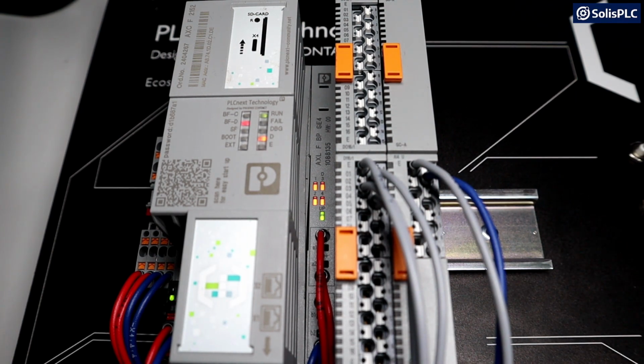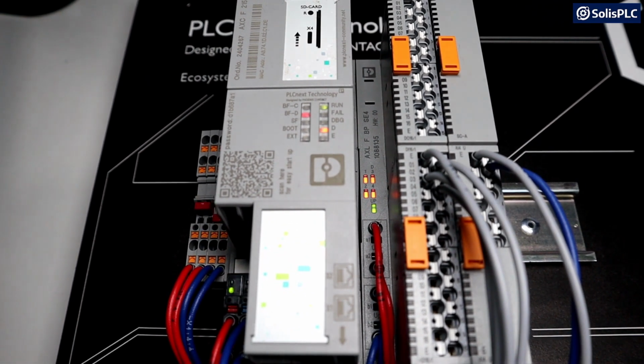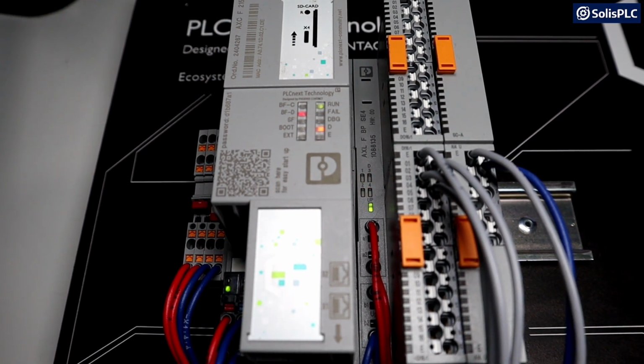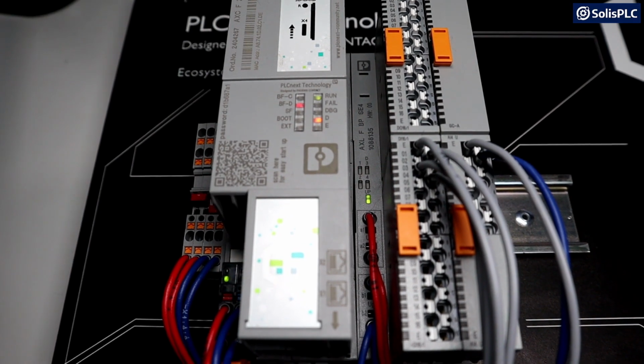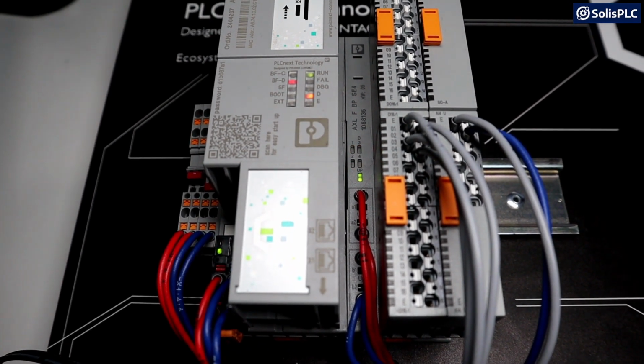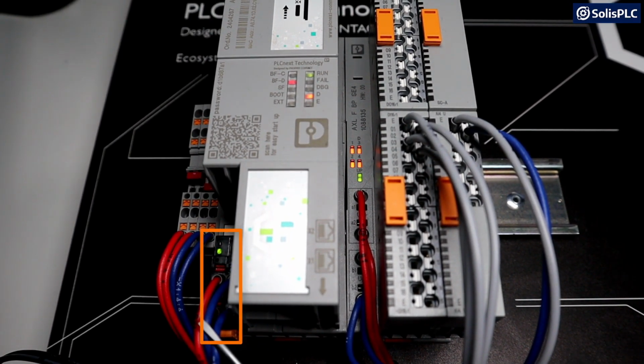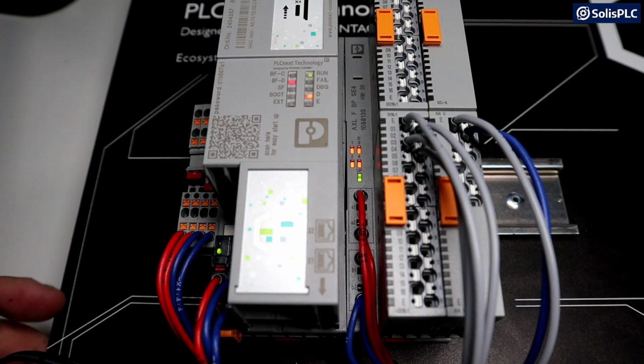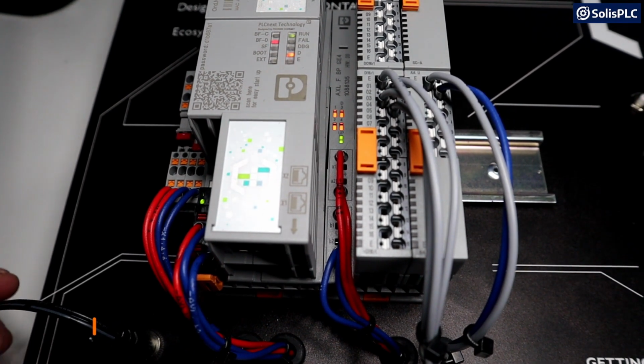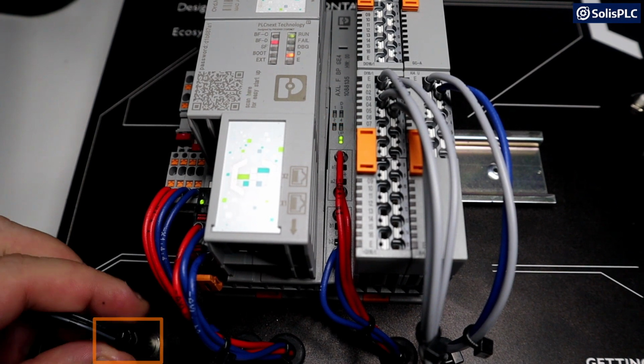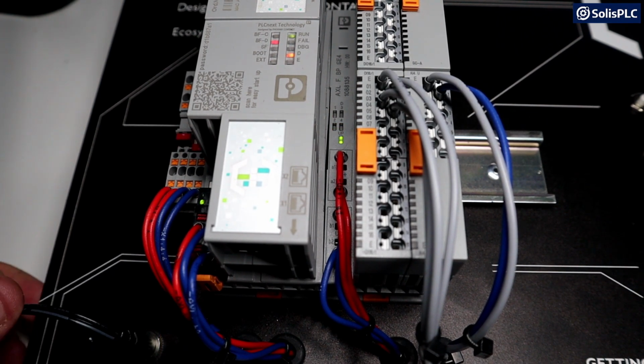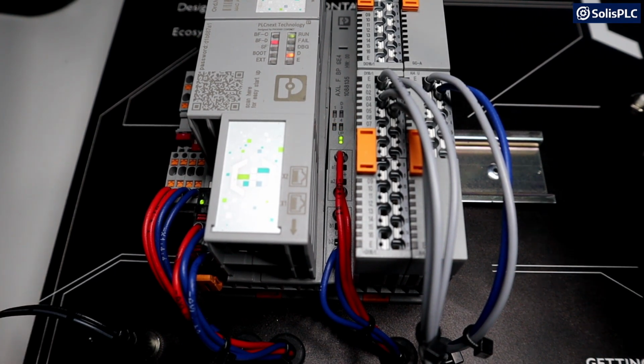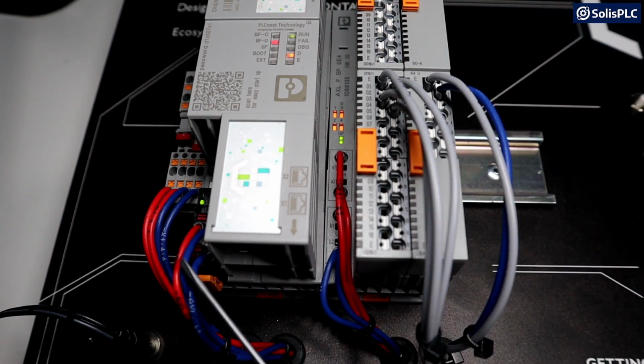Now, the two connections that need to be made to the PLC are going to be power and Ethernet. On the bottom left-hand side, you're going to notice two wires, one which is red and the other one which is blue, and that's going to be your 24-volt power. On the bottom left-hand side of the panel kit, you're going to have a plug with an adapter that comes in the kit. If you are using a PLC on its own, you're going to have to provide a 24 volts DC supply to the PLC.